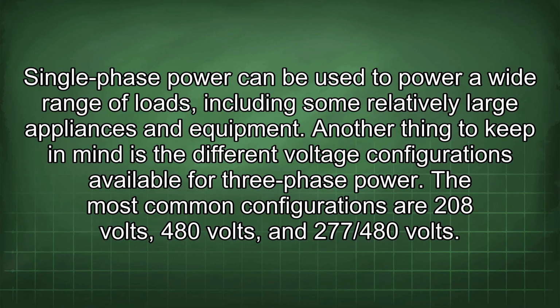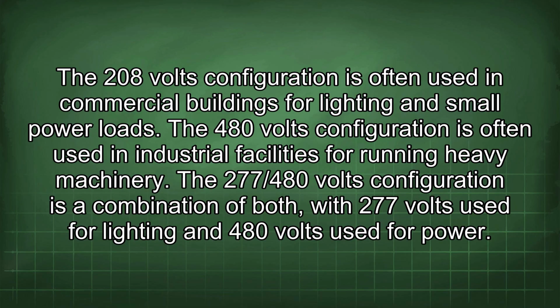Another thing to keep in mind is the different voltage configurations available for three-phase power. The most common configurations are 208 volts, 480 volts, and 277/480 volts. The 208 volts configuration is often used in commercial buildings for lighting and small power loads. The 480 volts configuration is often used in industrial facilities for running heavy machinery. The 277/480 volts configuration is a combination of both, with 277 volts used for lighting and 480 volts used for power.